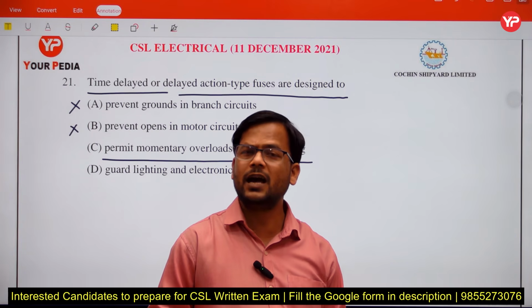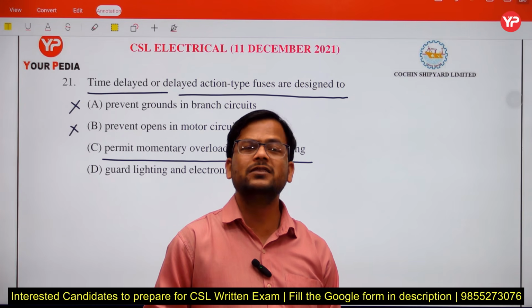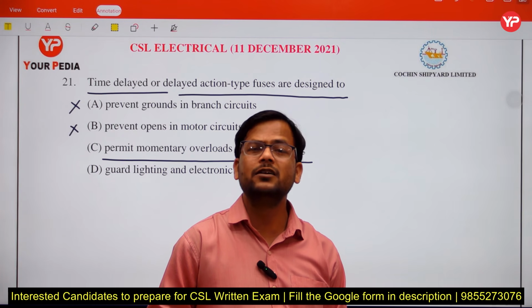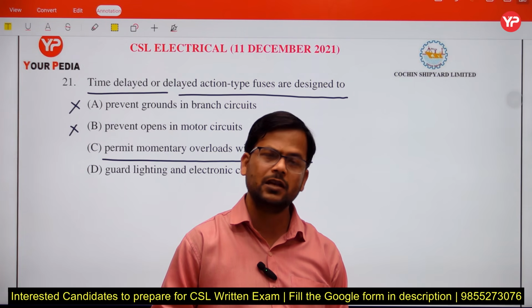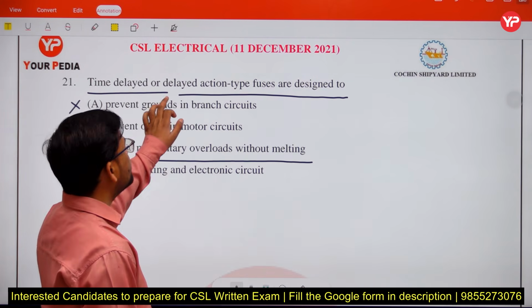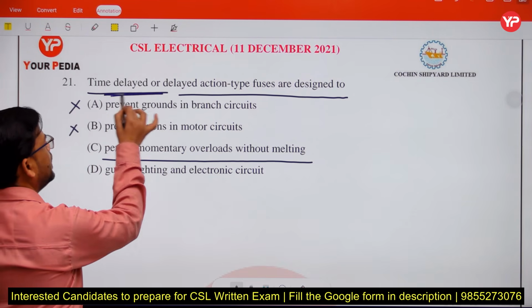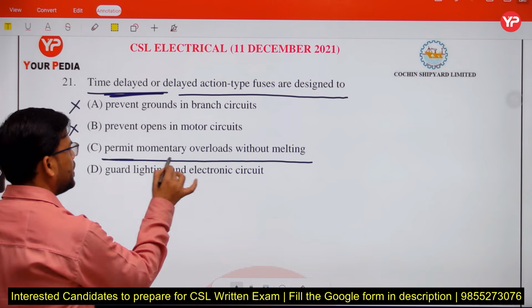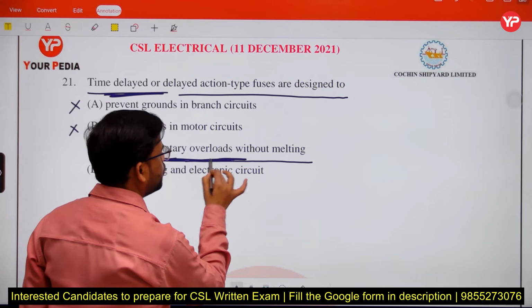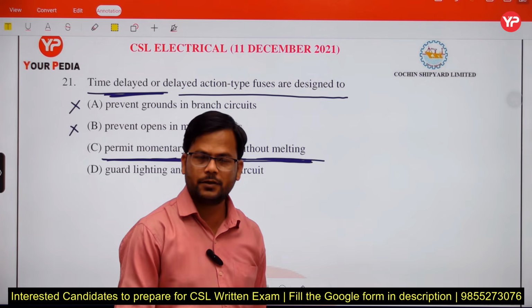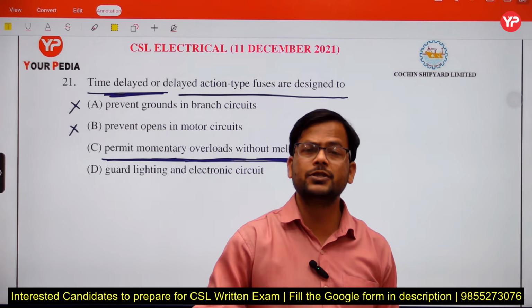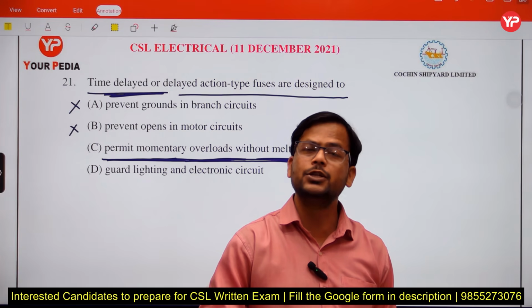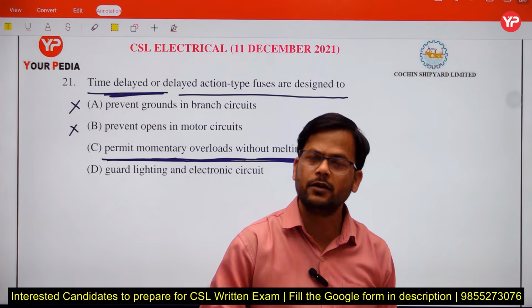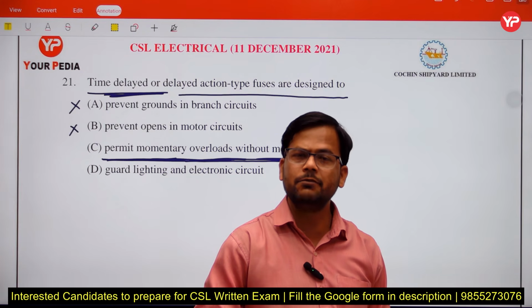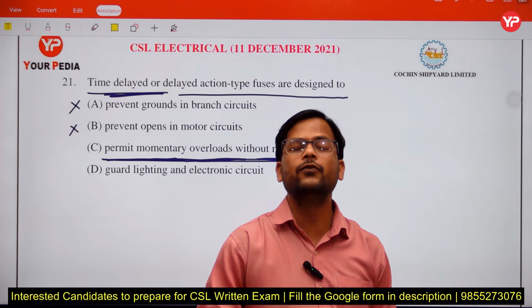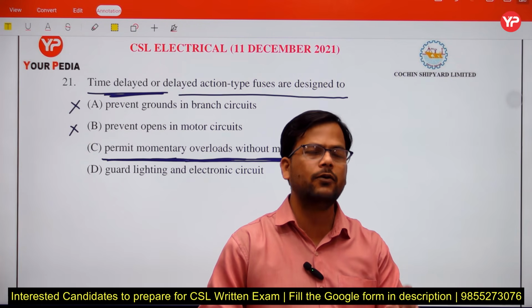So current is high, and if we use an ordinary fuse, this high current may melt it. To avoid this, we use a delayed action type fuse, which permits momentary overloads without melting. But if the overload is sustained for a long time, the time delayed fuse will still protect the instrument, as it only allows overload for a few instants of time.